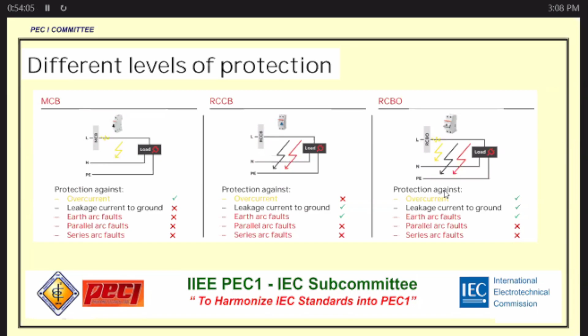So about residual current with overcurrent protection — maybe this is the first time you're seeing this. It only has 3 protections: overcurrent, leakage current to ground, and earth arc fault. That's the RCBO — it doesn't cover parallel and series arc faults.